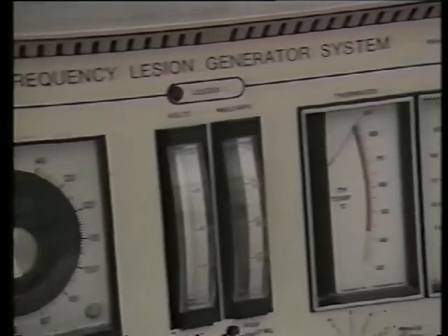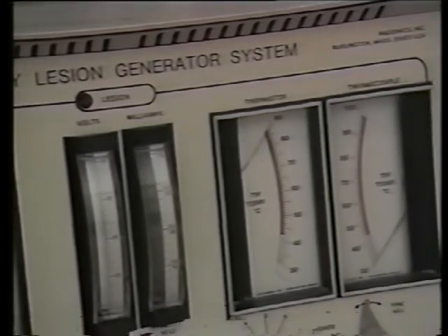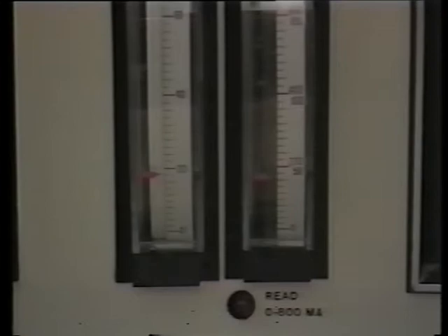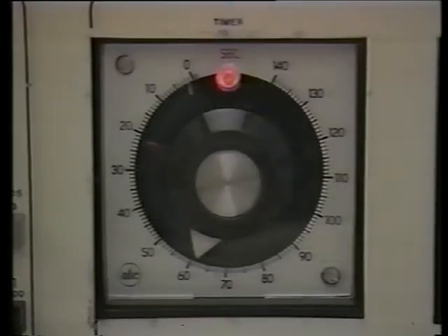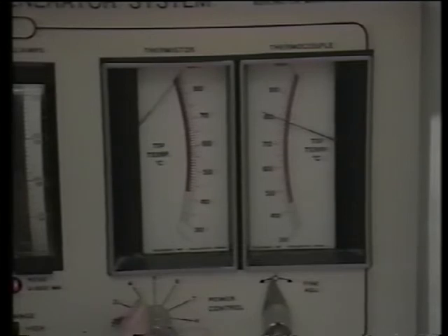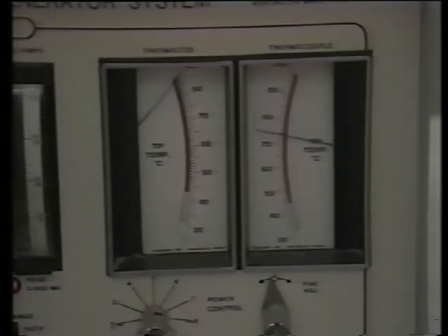Thirdly, there is the lesioning function indicating the output of radiofrequency current and including a time clock. And finally, there is the function of temperature monitoring. The temperature at the tip of the electrode can be measured with a thermistor or with a thermocouple.